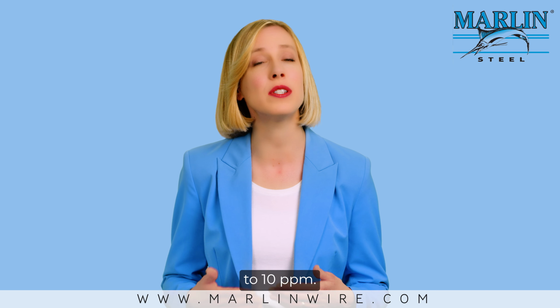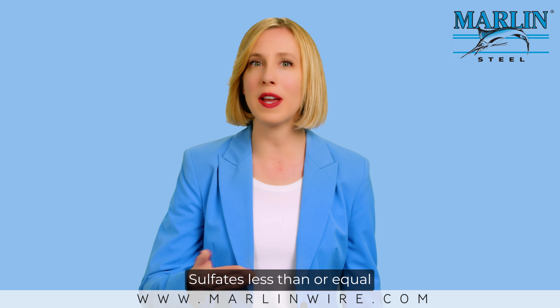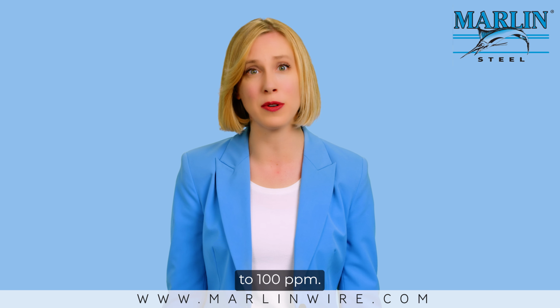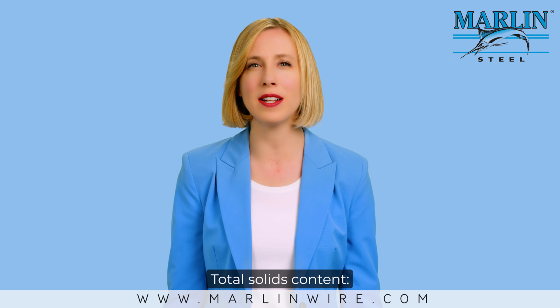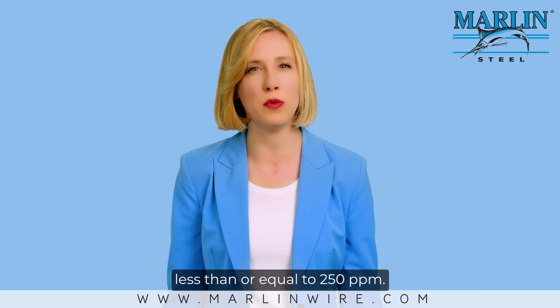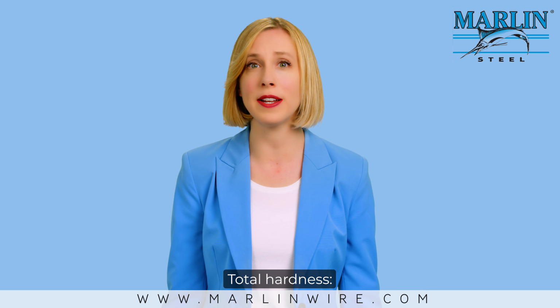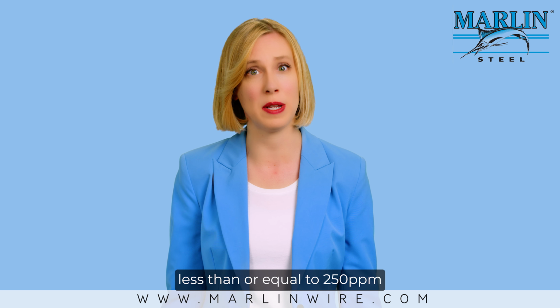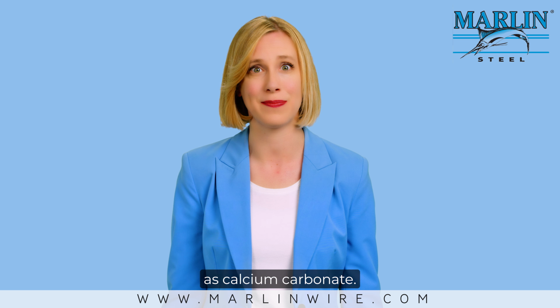Nitrates less than or equal to 10 ppm. Sulfates less than or equal to 100 ppm. Total solids content less than or equal to 250 ppm. Total hardness less than or equal to 250 ppm as calcium carbonate.